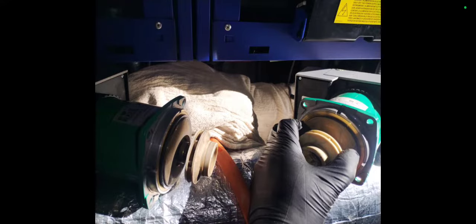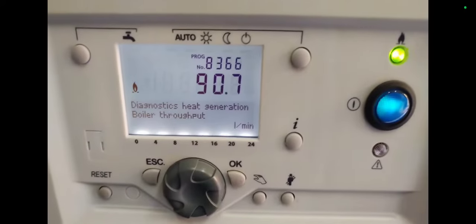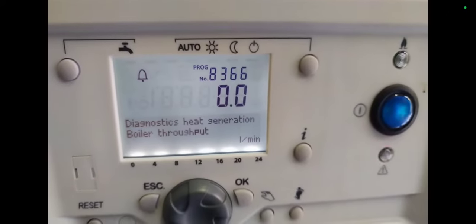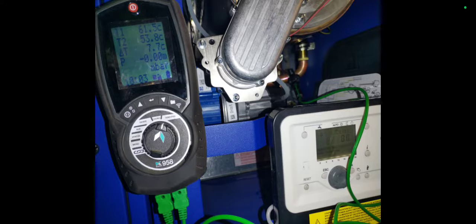I swapped pumps round. There was a pump on a boiler that was redundant, a boiler that had been isolated, so I took the pump off to swap it over for it to operate on this unit. And in the process I forgot the O-ring, and that caused me some trouble, but thankfully realized. So here's the unit, and I'm checking the flow rate. I also had my gauges. You can see my gauge over here.